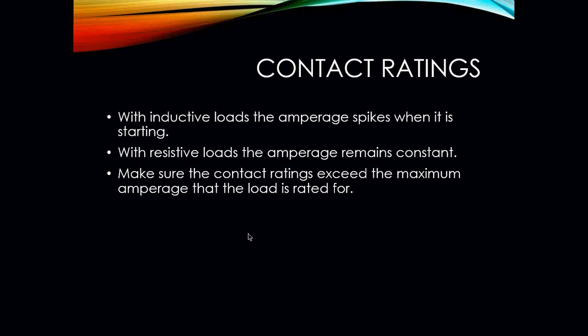With an inductive load, the amperage spikes when that motor initially starts. And if we're dealing with a resistive heater, the amperage is going to remain constant. But regardless of whether it's an inductive load or a resistive load, we need to make sure that the contacts are able to handle the amperage that's going to go through them. If we don't do that, the contacts are going to overheat, and they can actually weld closed, or they can weld open. Either way, we're going to damage the relay. So we need to make sure that the amperage is rated properly for whatever we're using that relay for.